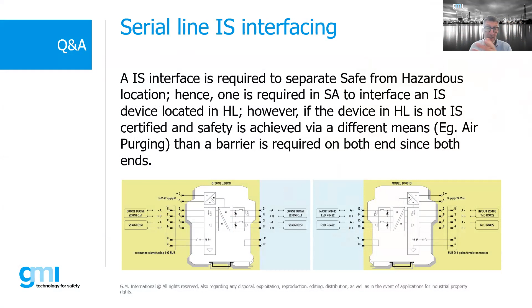Well, this is a tough one: how to use an IS barrier on TCP or other serial line communication, if we have DCS and control systems in different areas. I actually prepared an answer to this. You have to create a bridge across from the safe area to the hazardous area using two devices talking to each other, with the barrier in the middle. Suppose you're crossing a hazardous location from safe to safe—that's the solution you'd have to use.